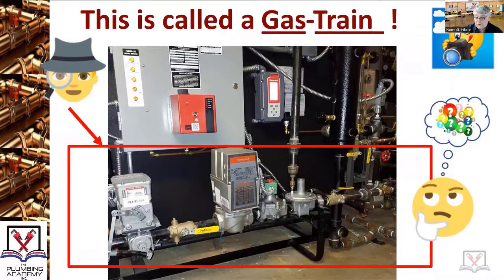This is how it gets installed. You're not putting copper — you're using all steel. You have a regulator that's vented to the outside, just in case that diaphragm fails.